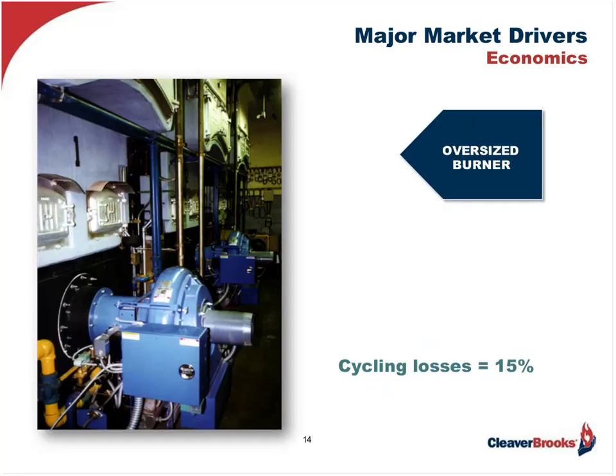Or, in the case of the burner-boiler package where it's oversized due to a cutback in load, this causes the burner to cycle inordinately. When it does, the cycle costs due to pre- and post-purge losses can easily equal 15%. When you have a fuel bill averaging $725,000 per year for a 400-horsepower boiler operating about 4,300 to 4,400 hours per year, that's over $100,000 a year.